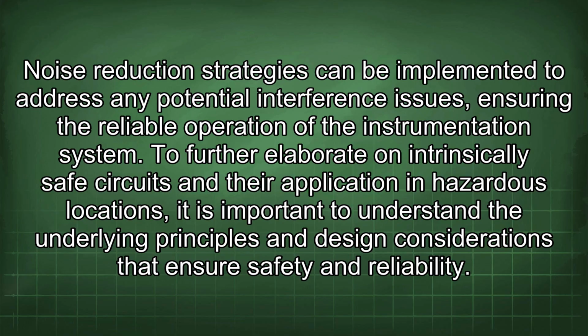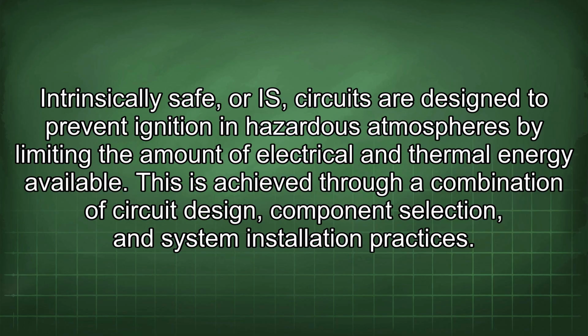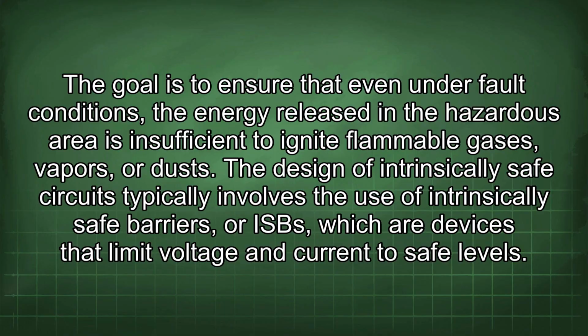To further elaborate on intrinsically safe circuits and their application in hazardous locations, it is important to understand the underlying principles and design considerations that ensure safety and reliability. Intrinsically safe, or IS, circuits are designed to prevent ignition in hazardous atmospheres by limiting the amount of electrical and thermal energy available. This is achieved through a combination of circuit design, component selection, and system installation practices. The goal is to ensure that even under fault conditions, the energy released in the hazardous area is insufficient to ignite flammable gases, vapors, or dusts.